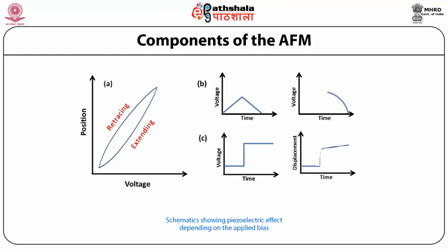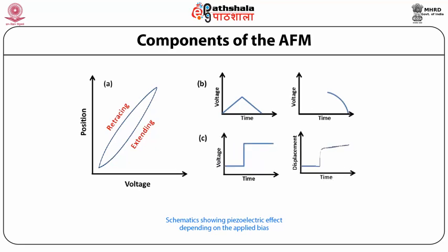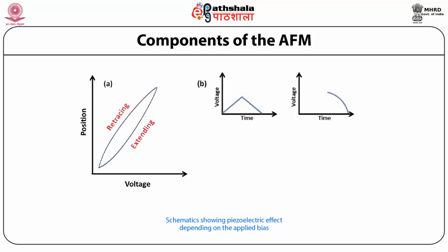Creep is the result of this slow movement of the piezo over the remaining offset distance once scanning is resumed. Creep appears in the image as an elongation and stretching of features in the direction of the offset for a short duration of time after the offset.